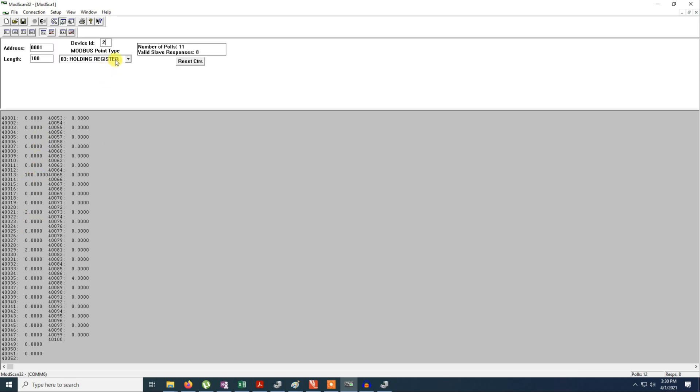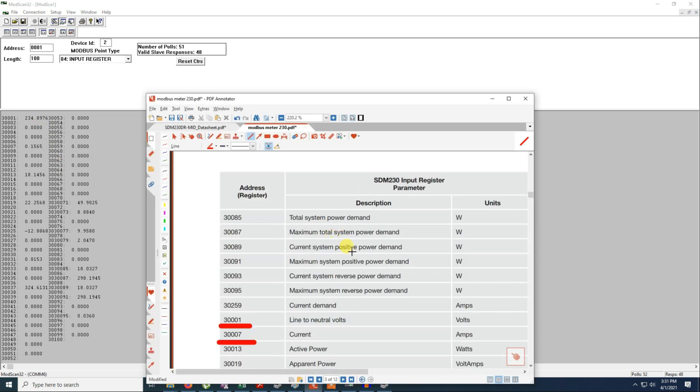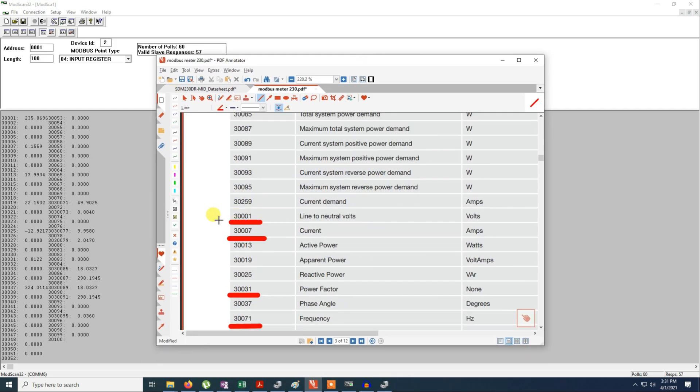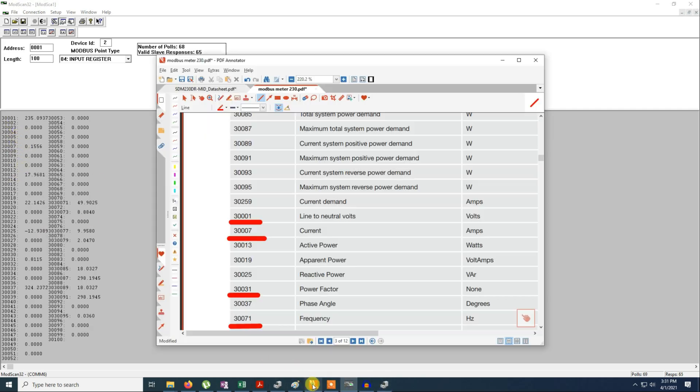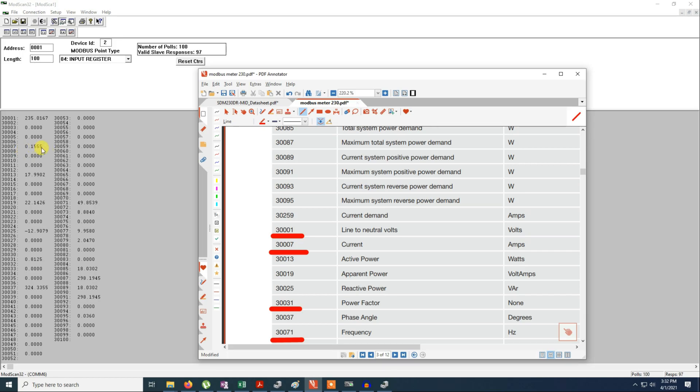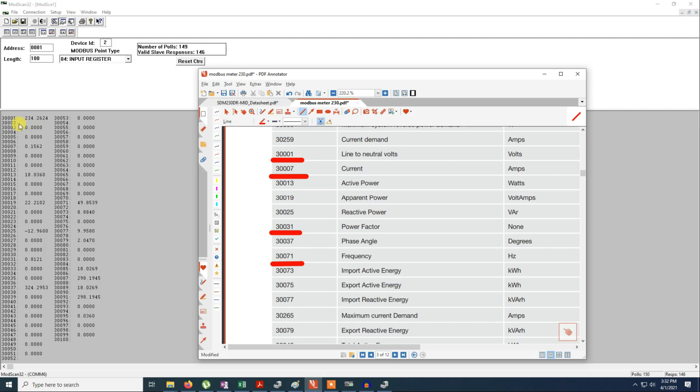And right now you can already see that I can read some parameters. To read the voltage current we should go to the input registers. So right now you can see that the voltage which is here 235 actually. As I said, we have to refer to the MODBUS registers data sheet. So for the voltage 30001, you can see the voltage. I will just bring it back. So this is the voltage. And now for the current, we should go to register 30007. So we go to register 7. You can see the current which is here 0.155. So for the power we should go to register 13. So here you will have the power. In fact you will see that address 1 is being used and address 2. But why on the other address you don't have anything? This is why.